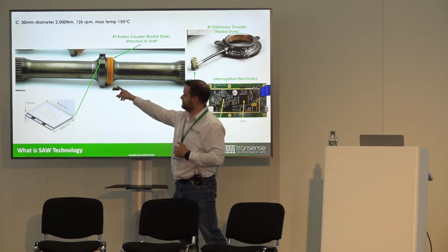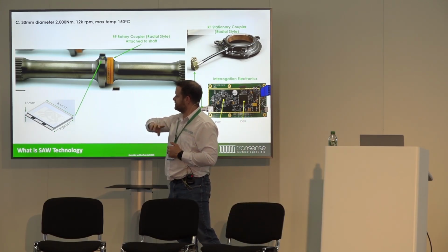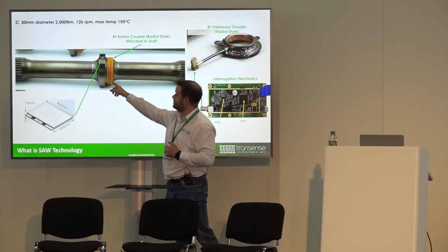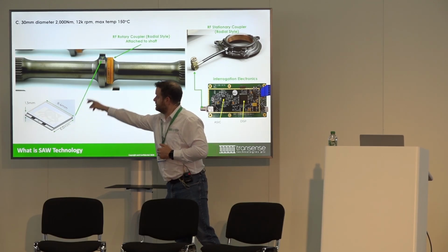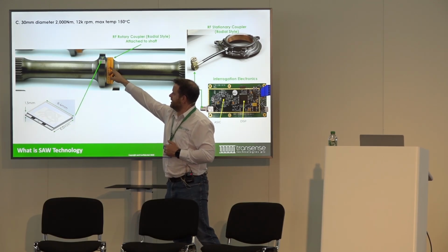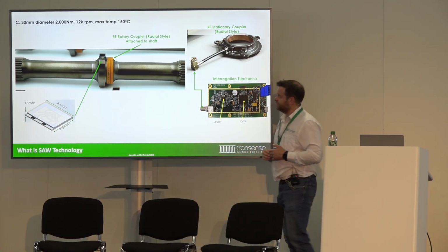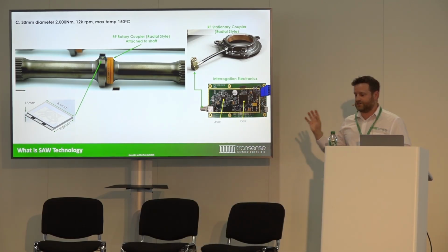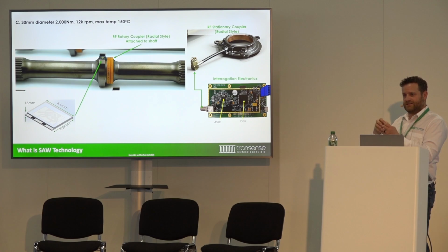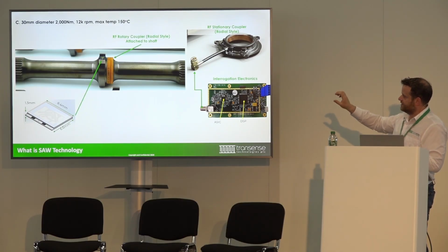This is a different style of RF coupler to the previous slide - what we call a radial coupler. The sensor installation is mounted in this area of the shaft. A key feature of that shaft is you'll notice the diameter is swollen slightly, and that's because with the SAW technology we're optimizing the strain that the sensor is seeing in that location.